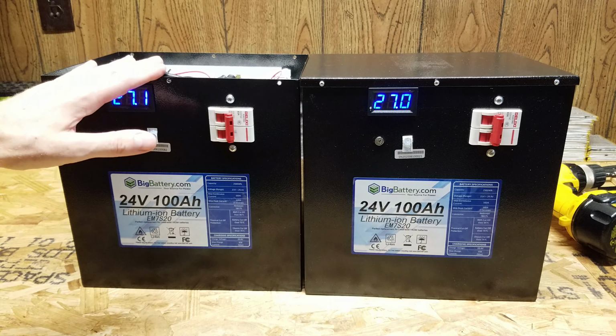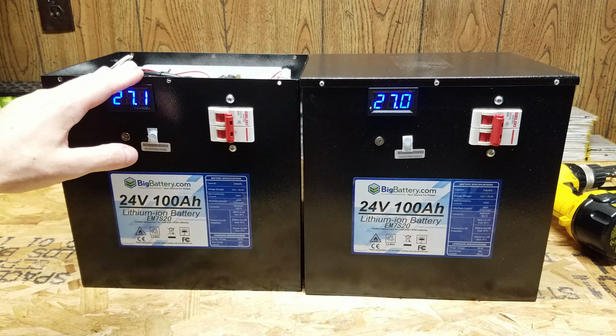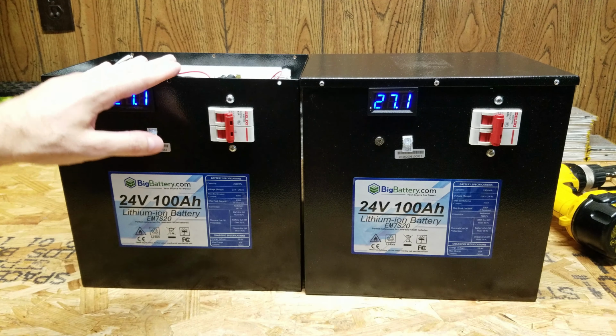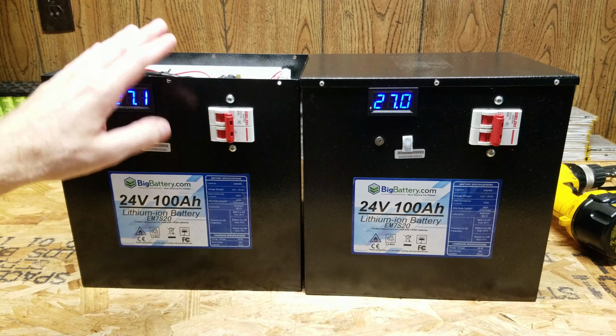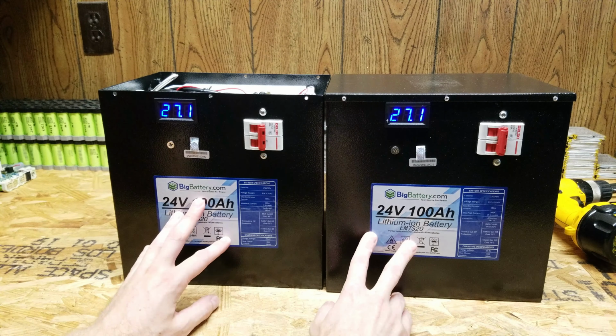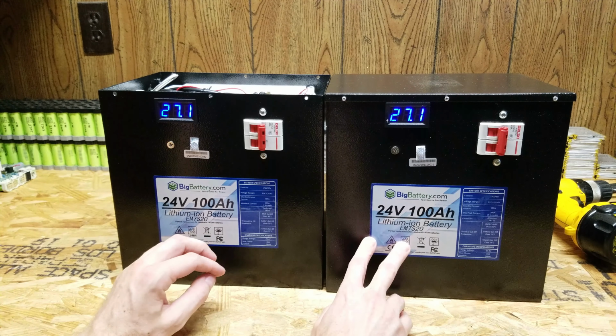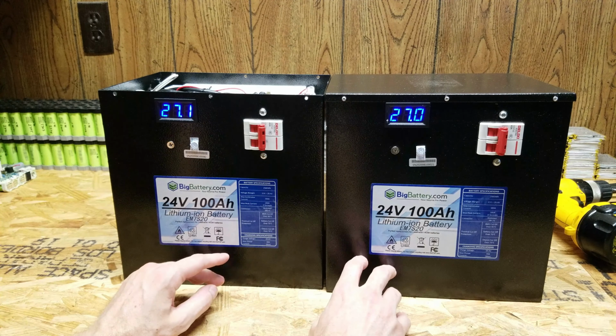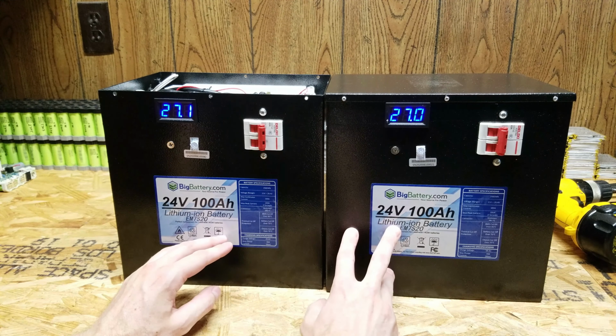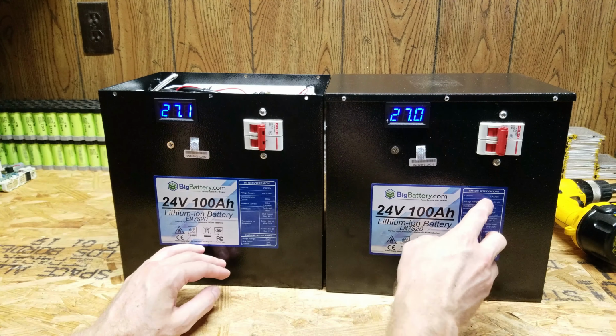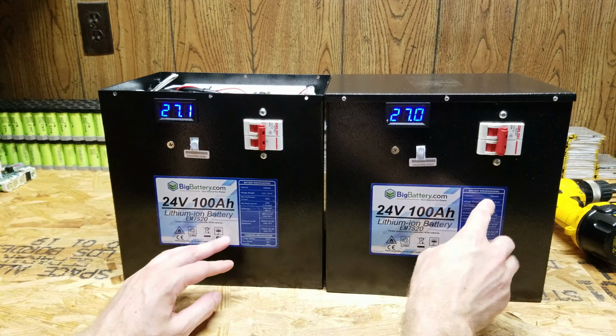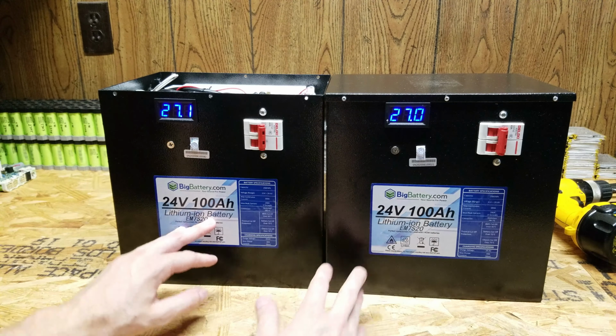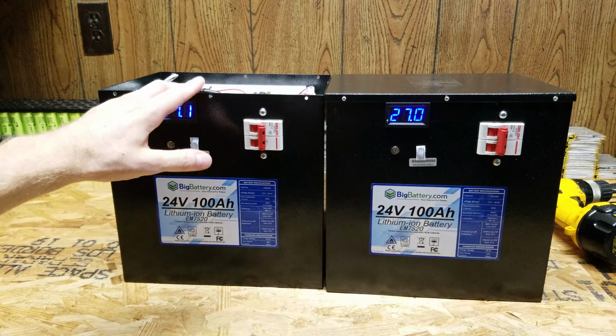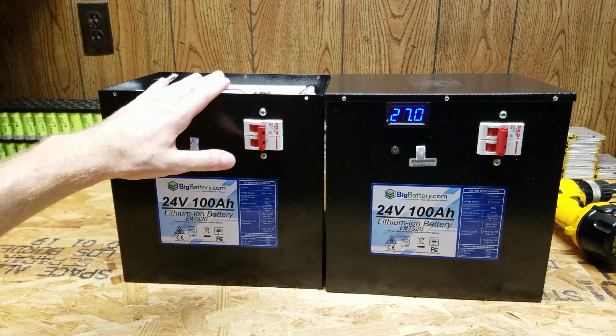I'm going to leave the lid off of this battery enclosure because I want to take the thermal cam on it while I'm testing it and see what the temperatures are inside. I'm going to connect them to my inverter and run a heavy load, probably the air conditioner or the clothes dryer. I want to measure the amount of power these put out, whether it actually meets the 2.5 kilowatt hour that it's rated, and also see what kind of heat is generated inside the enclosure. I think that will definitely be a pretty thorough test of these.